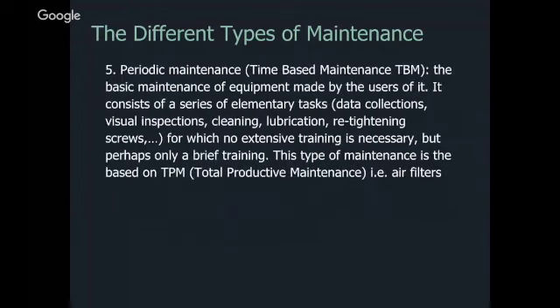Periodic maintenance is time-based maintenance — probably the most common and the most basic, with elementary tasks you can assign to entry-level techs without heavy training. A great example is an air filter: time-based maintenance means every three months you go into each specific air handler or fan coil and change out the air filter. It's based solely off time, not condition.